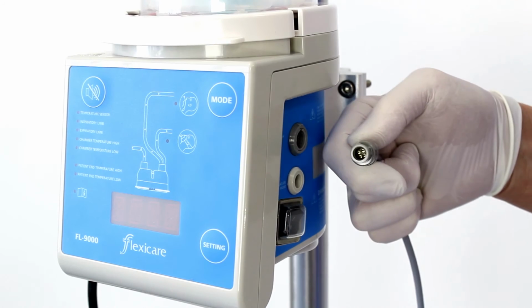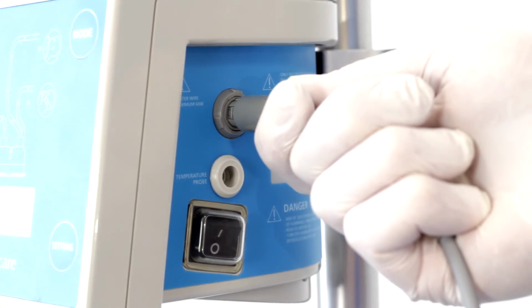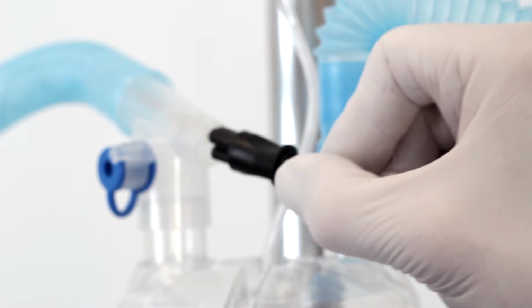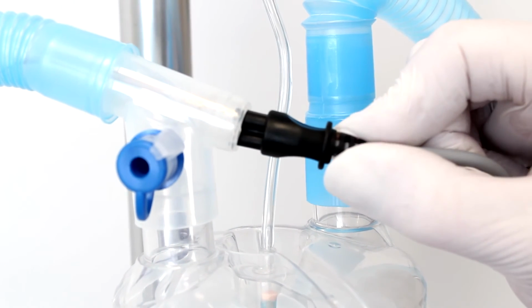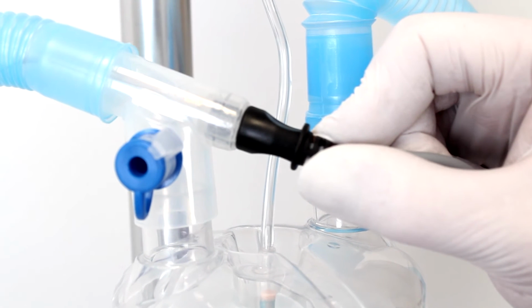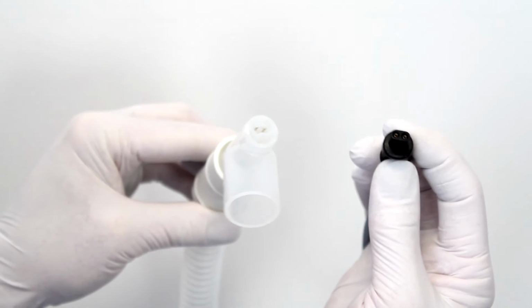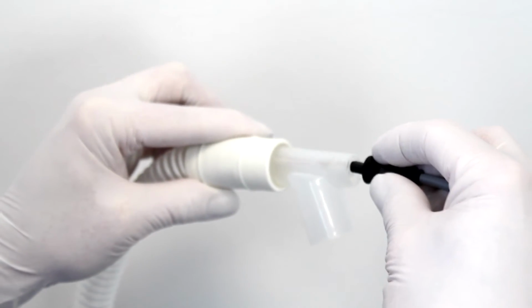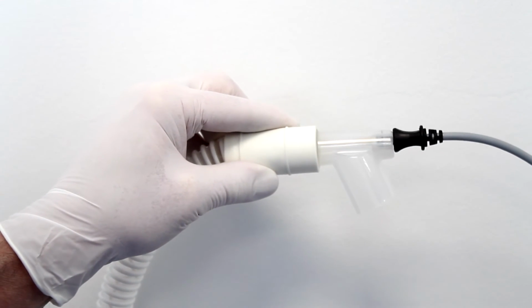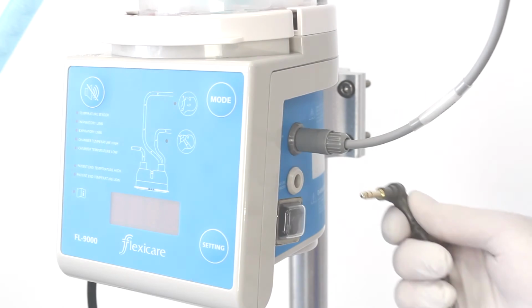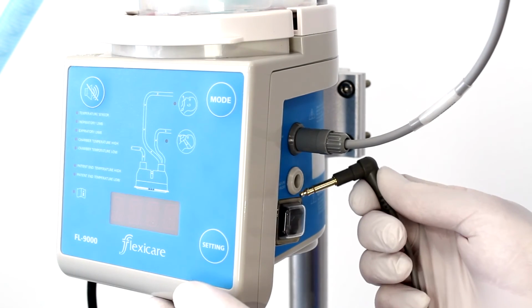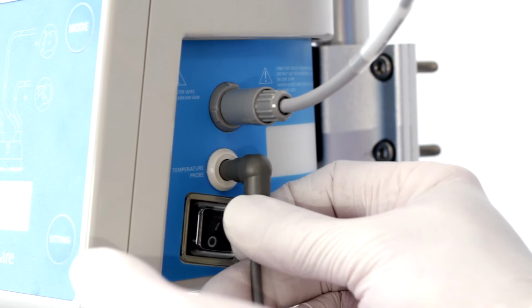Connect the heater wire lead to the DIN socket on the right side of the FL9000. If using a dual heated wire adapter lead, as in this case, the shorter of the two leads is inserted into the cloverleaf connection on the elbow of the inspiratory limb. The longer lead is connected to the elbow at the ventilator end of the expiratory limb if a dual heated wire limb is being used. The temperature probe lead is then inserted into the jack socket on the side of the FL9000.